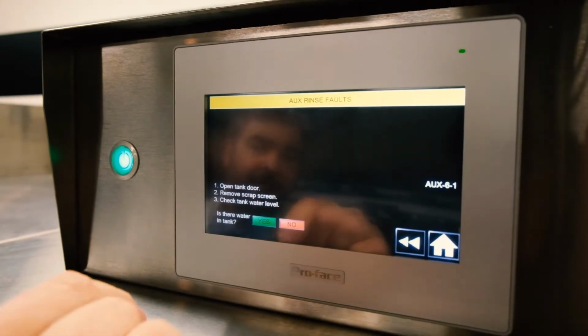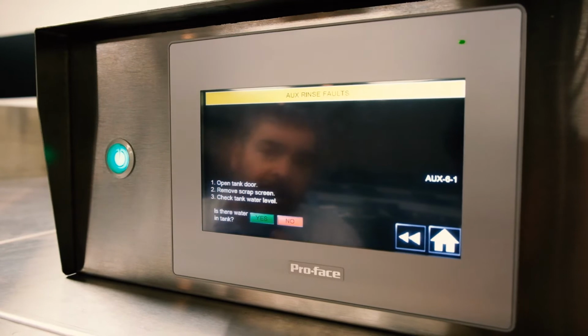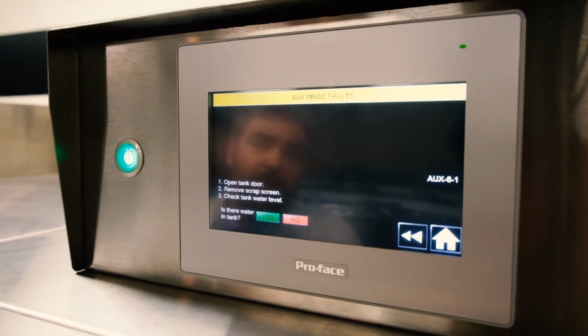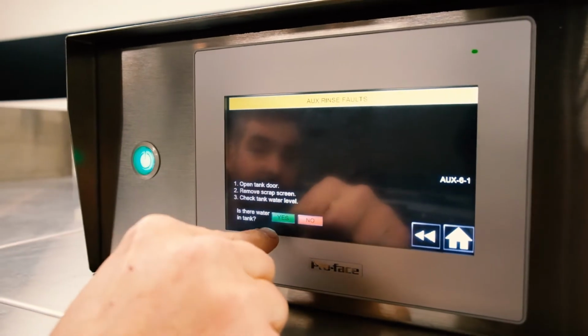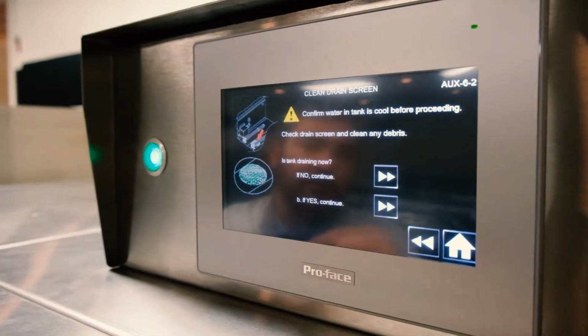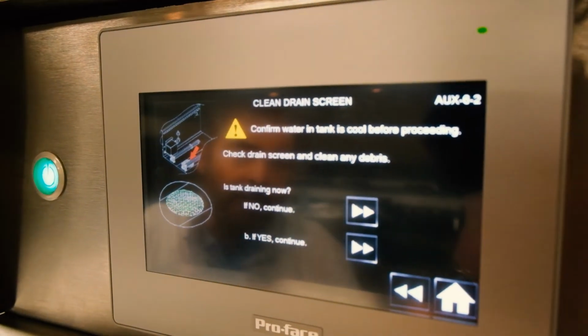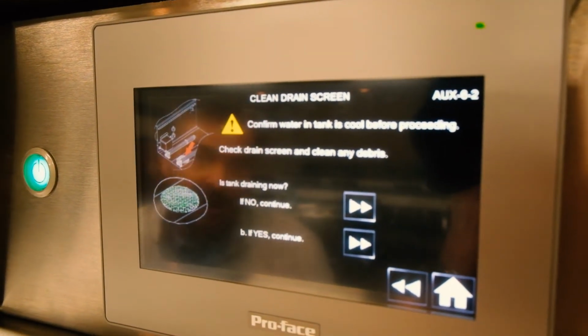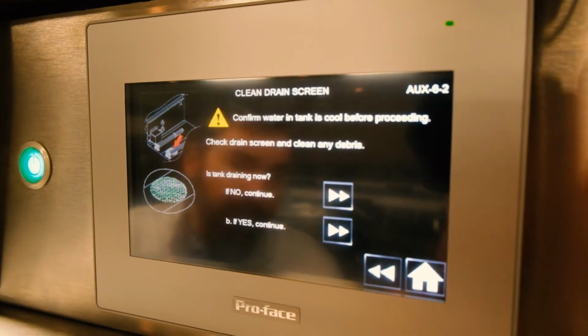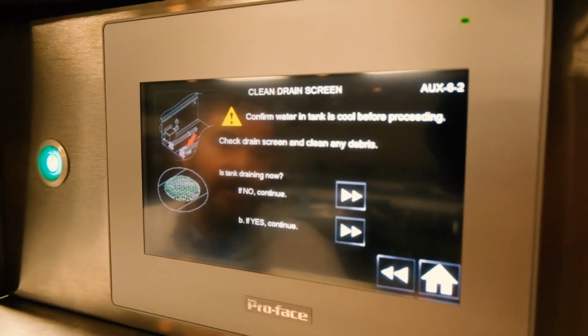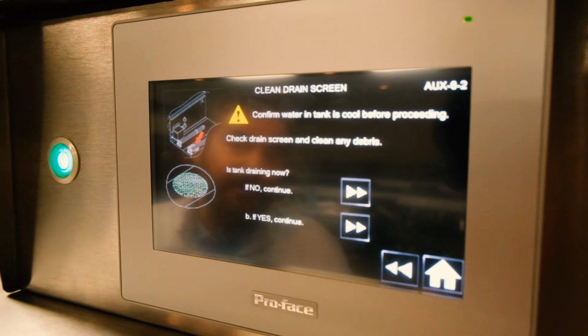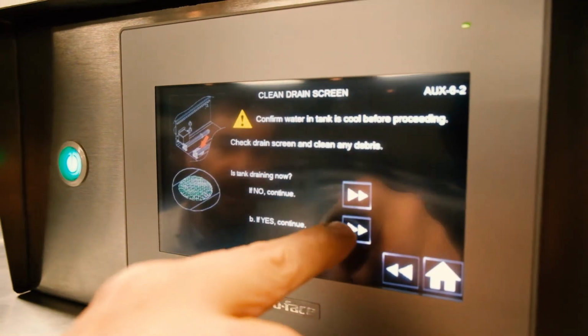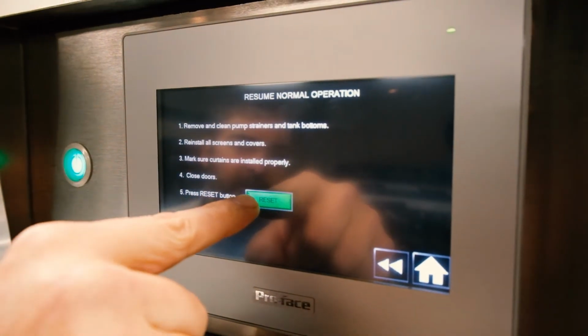You press that, and it tells the operator to open the tank door, remove the screen, and check the tank water level. Is there water in the tank? Hit yes. It then tells the operator they probably just need to clean the screen and check the drain screen to make sure there's no debris there. Is the tank draining now? If it is, hit yes, and then press this to reset.